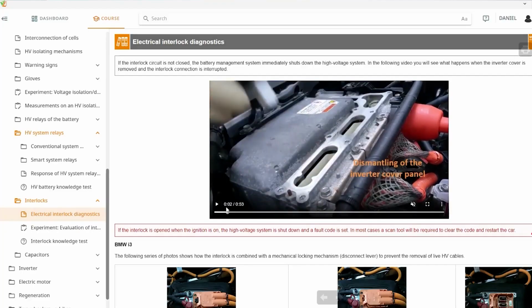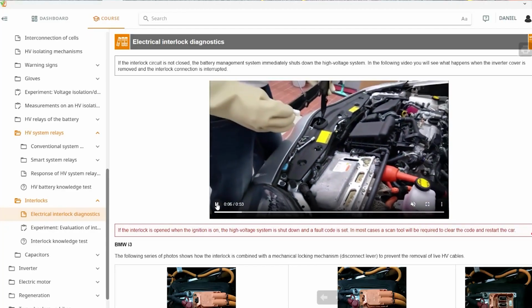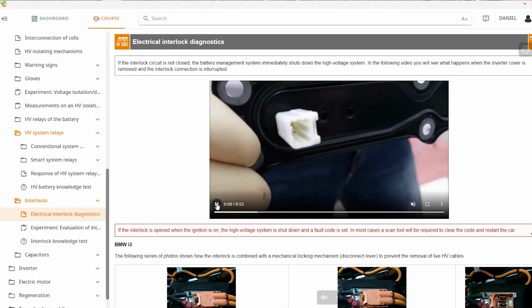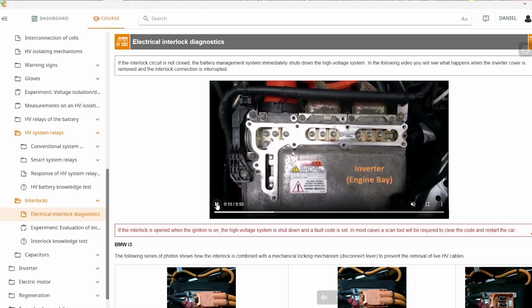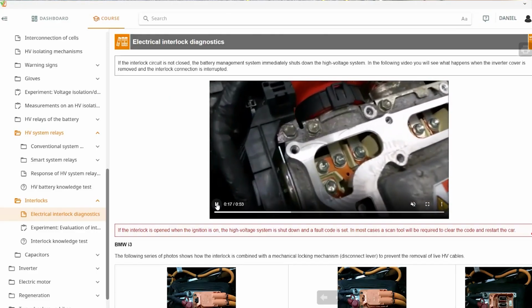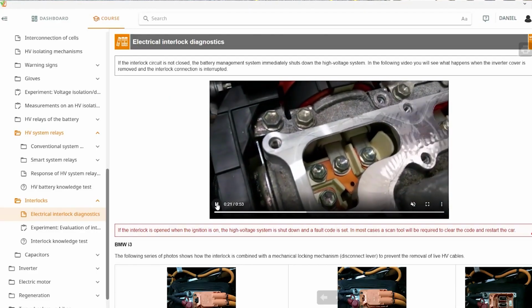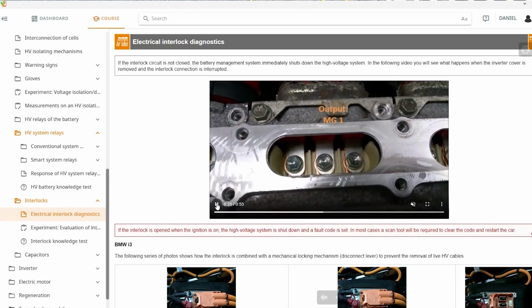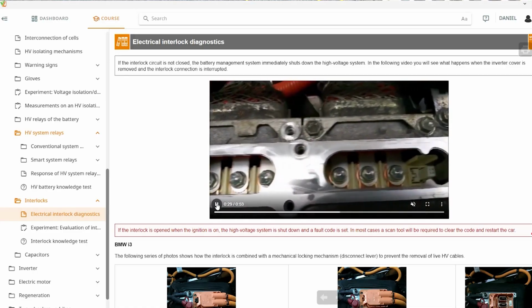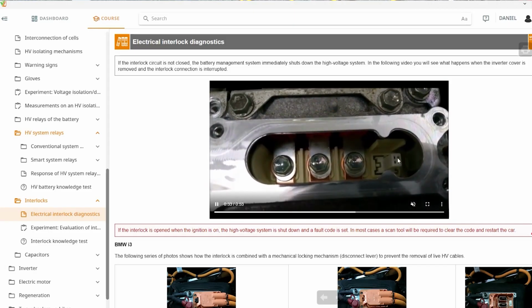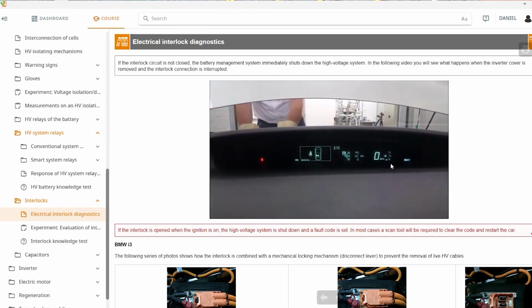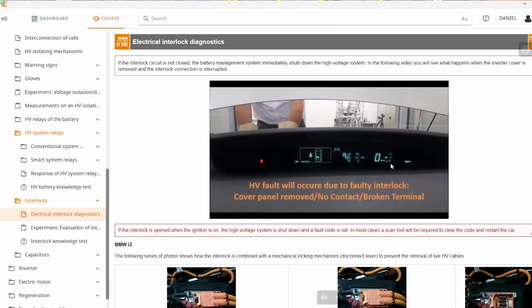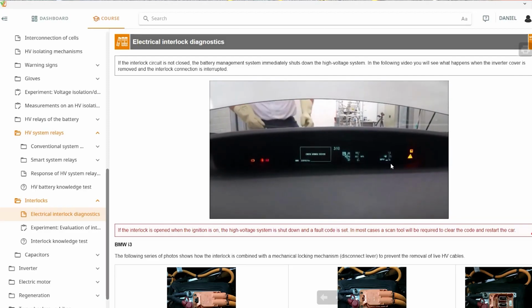If we look within our LabSoft course for this unit, we also have examples where the interlock is on a cover. Here it's part of a current carrying system, so the cables or the manual service disconnect. But in this case, we see it's just a bridge connector that's part of the cover. This is from a Toyota Prius. Right at the end here we can see this little connector, and that's our interlock. The bridge connector was on the cover, so when you take the cover out, you actually open that bridge connector and interrupt the interlock. The goal is always that when you open something, you interrupt the interlock before you're able to touch anything that has to do with high voltage.